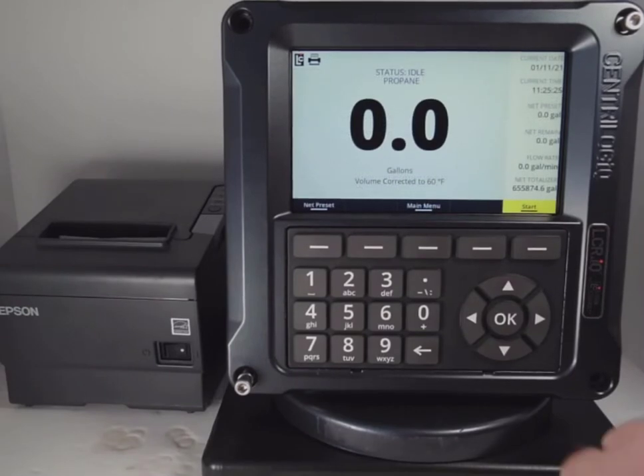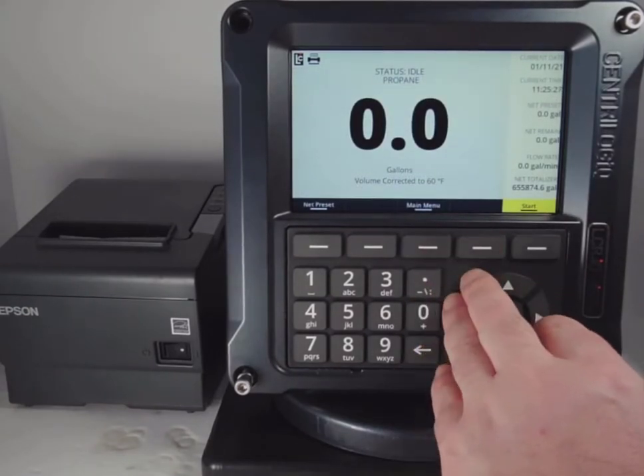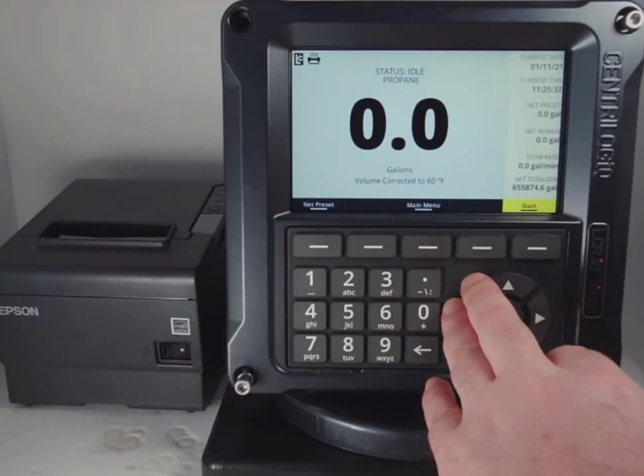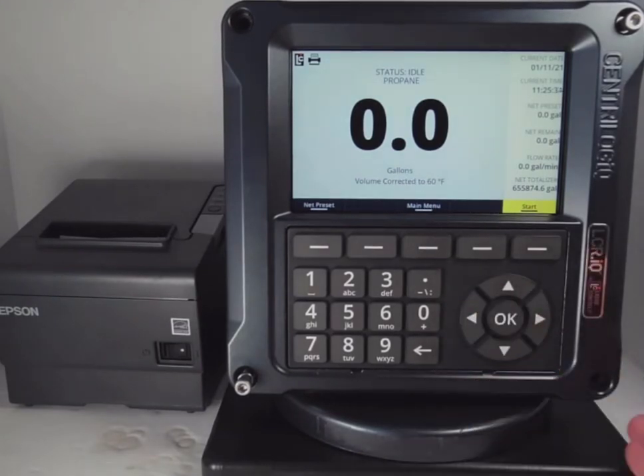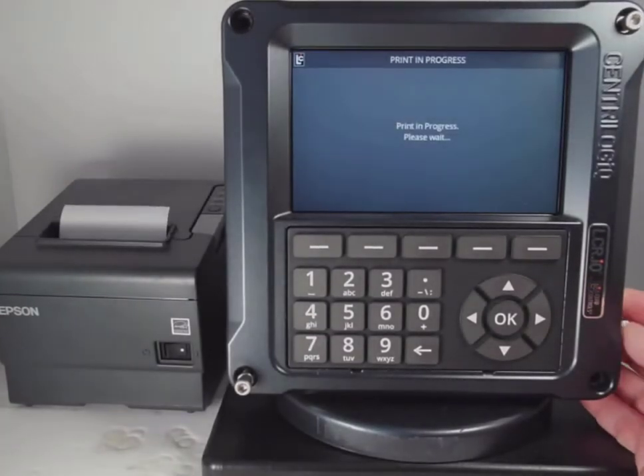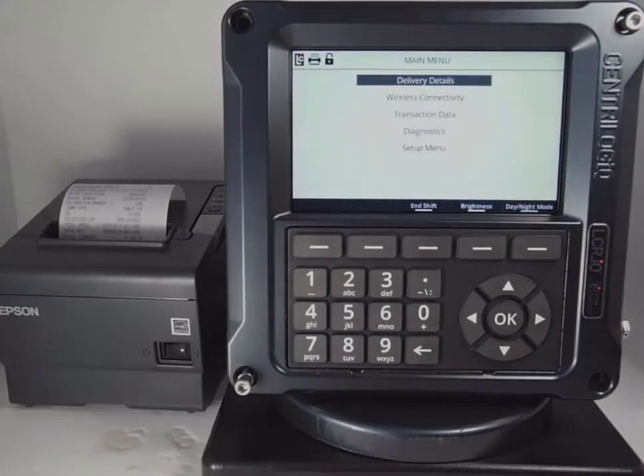The other option for viewing the About screen is through the Update Software section. To do this, you must be in calibration mode. So the first thing we'll do is put the register into calibration mode by rotating the bolt on the side of the register counterclockwise. This will put the register in calibration mode.